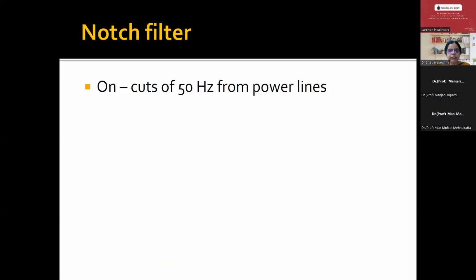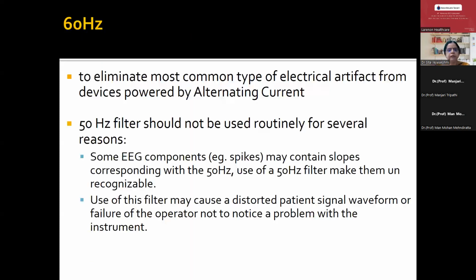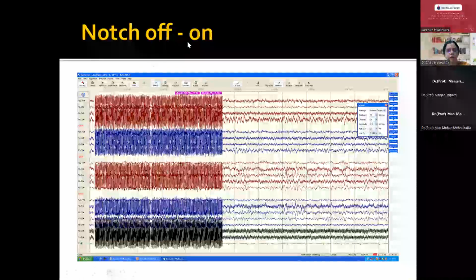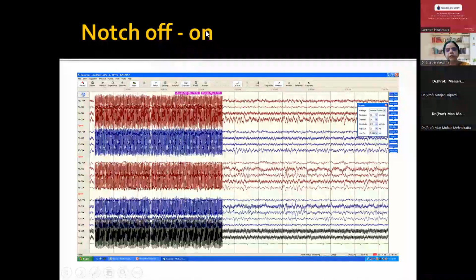Then the next filter is the notch filter. Why are we using the notch filter? Normally we get a lot of noise coming from the electrical power lines. So the notch filter will cut off the 50 hertz frequency, which is in India, and the 60 hertz frequency from the USA. Actually, this is what is in the power lines. Normally the notch filter should be off only. But whenever you are getting a lot of noise, especially if there are power lines close to the lab, then the notch filter has to be on. And this is just to show that when the notch filter is off, you can see that there is a lot of noise coming. Immediately when we change the notch filter to on, you can see the noise is gone.